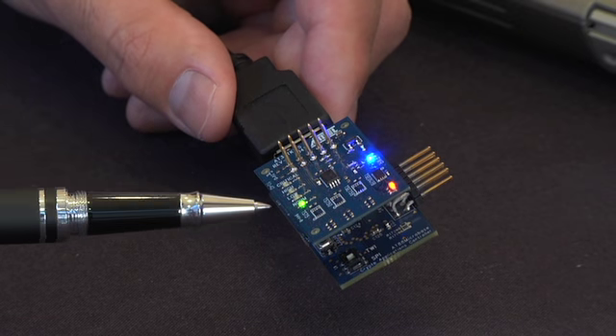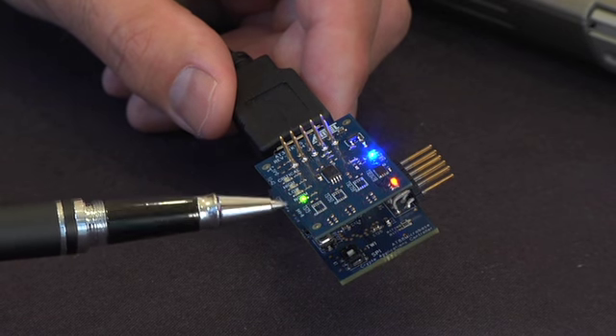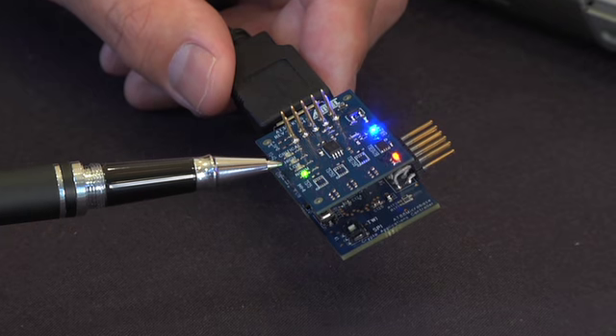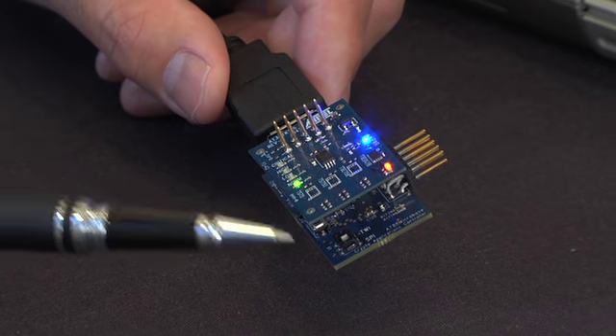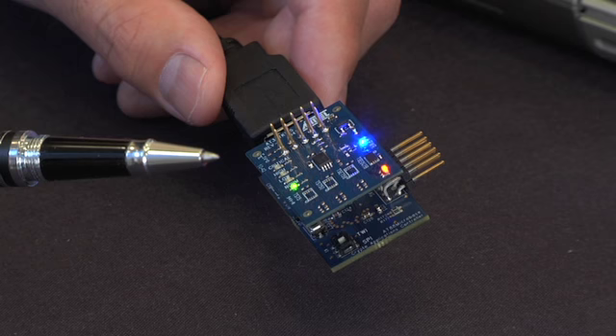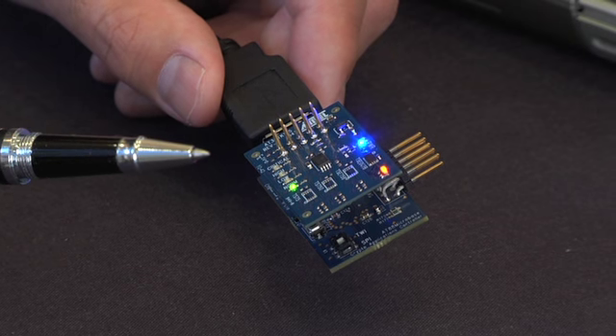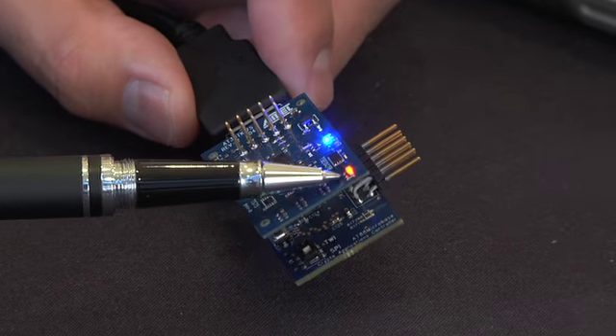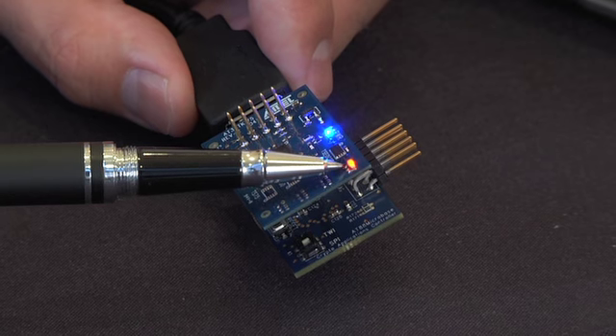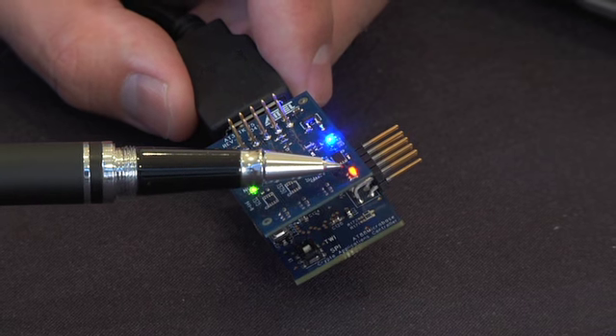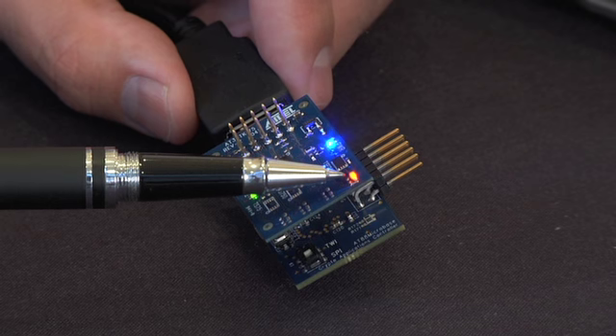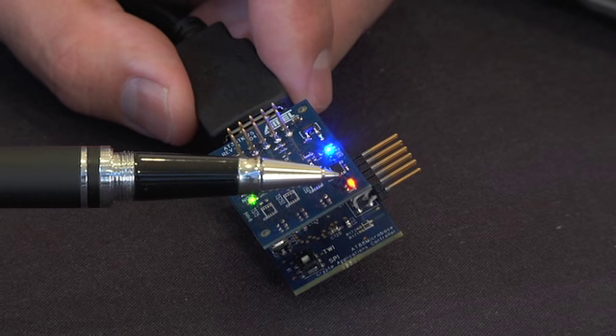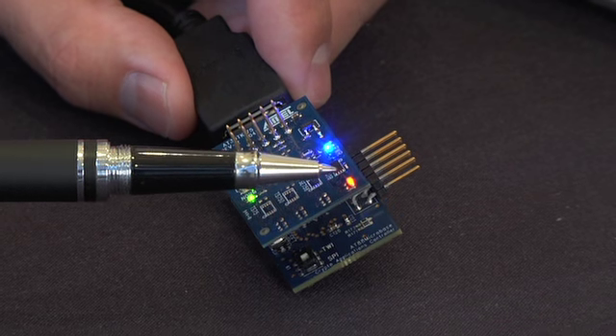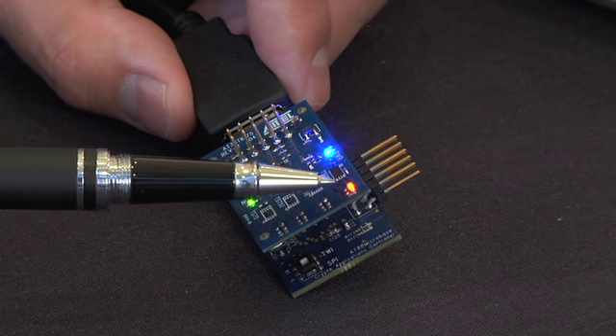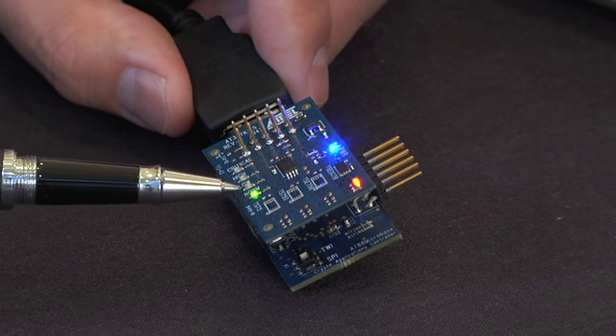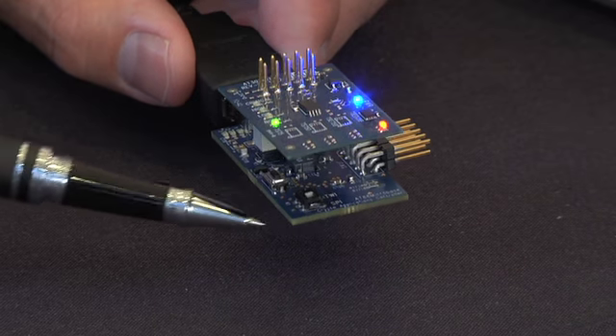Also on this board we have some status LEDs that tell us when the temperature is in a normal condition or when it exceeds the low alarm limit or high alarm or critical alarm. And then this red LED is used to indicate certain temperature events and what's happening with the device itself. So this LED here is driven by the temperature sensor itself. It's a direct connection to the device's event pin, and that event pin is used to signify when a temperature threshold has been crossed in either the positive or negative direction, going up or down. And then these LEDs here are actually being driven by the microcontroller itself on the communication board.